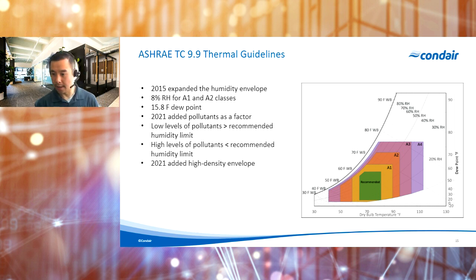Perfect. Thanks, Sean. There's another question here I can answer, asking about the velocity of air restrictions across the mediums. So, as I mentioned, when we're talking direct evaporative systems or adiabatic systems in general, especially if we're going inside of a duct or an air handler or some sort of plenum, air velocity is going to play a big role in terms of efficiency and potential for carryover.